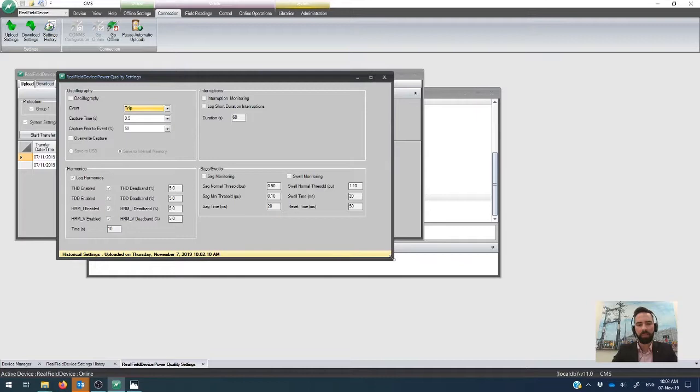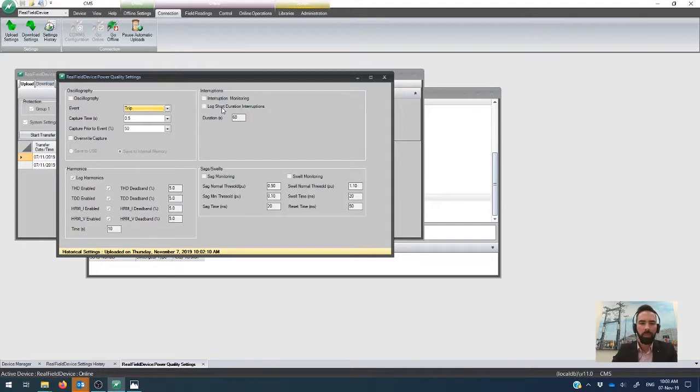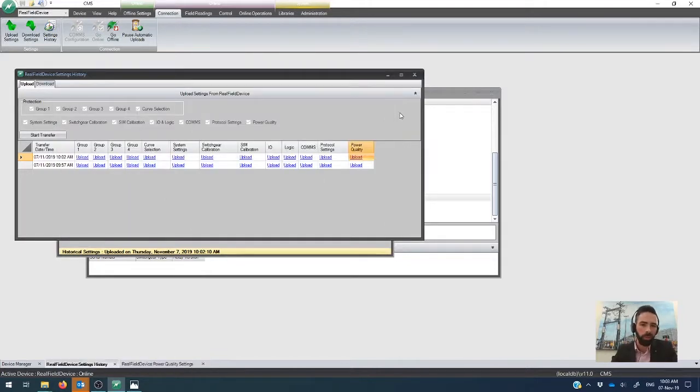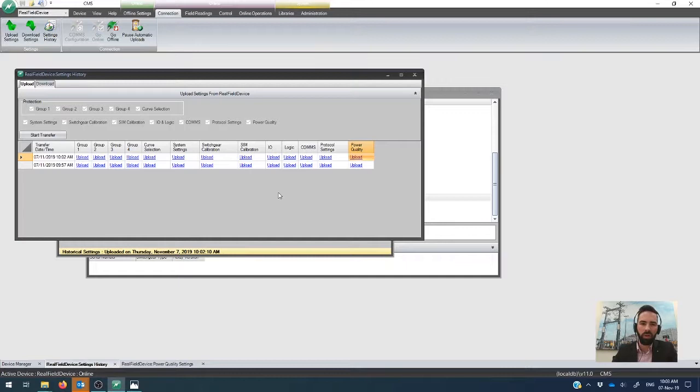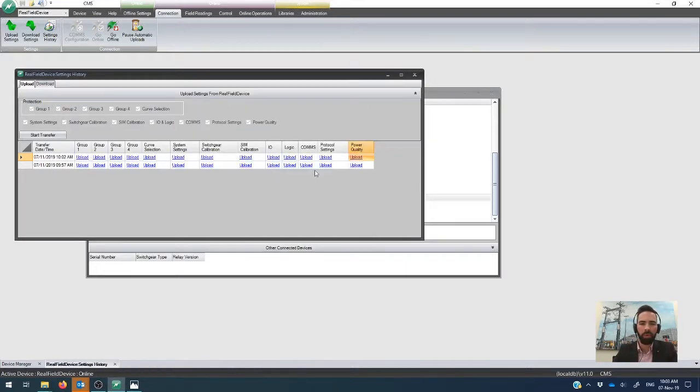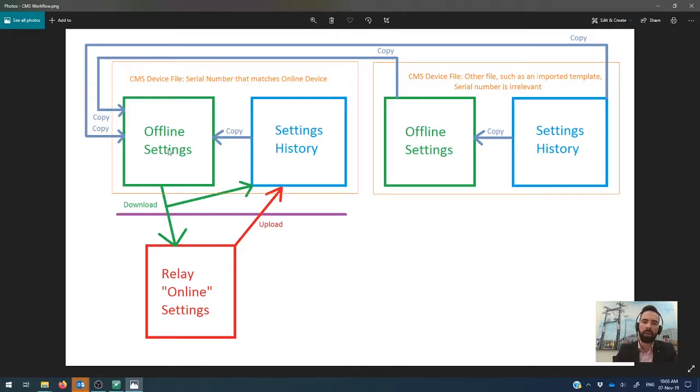Now, to new users of CMS, they often wind up in this place and then try and change individual settings and say, oh, sorry, why is it not accepting the changes? But that's because this is your historical log. You can't change the settings history, and that's because you don't want to corrupt the old history. If you actually want to edit the settings that's in the controller, then what you need to do is you have to bring what you've uploaded across to this offline settings component here. So in other words, we're going to copy from what we've uploaded into the offline settings, which actually overwrites the state of the offline settings for that device file. So let me show you how to do that.